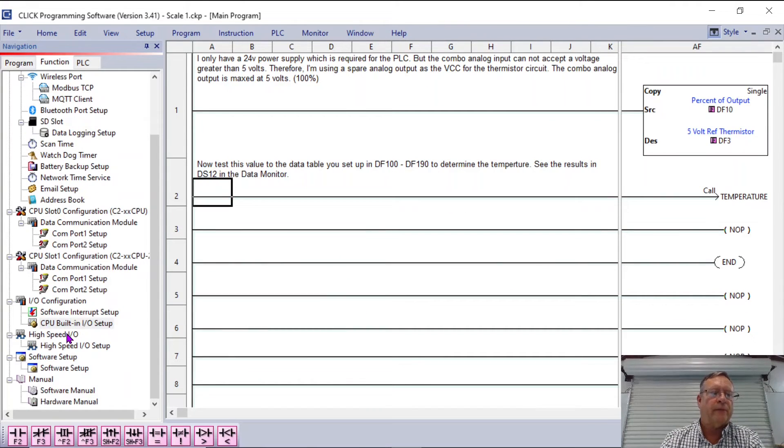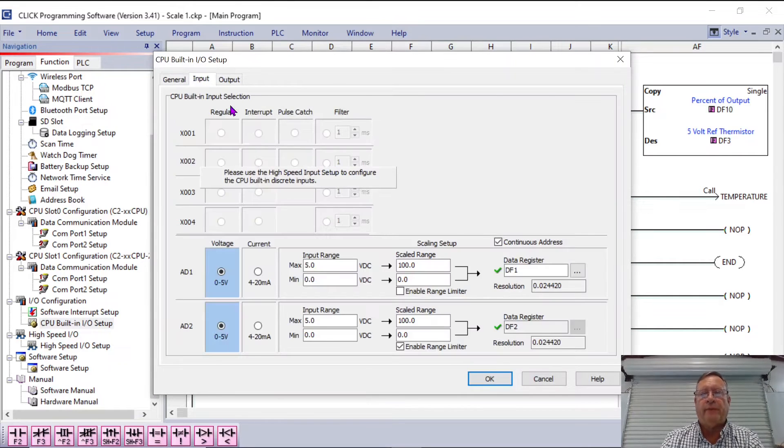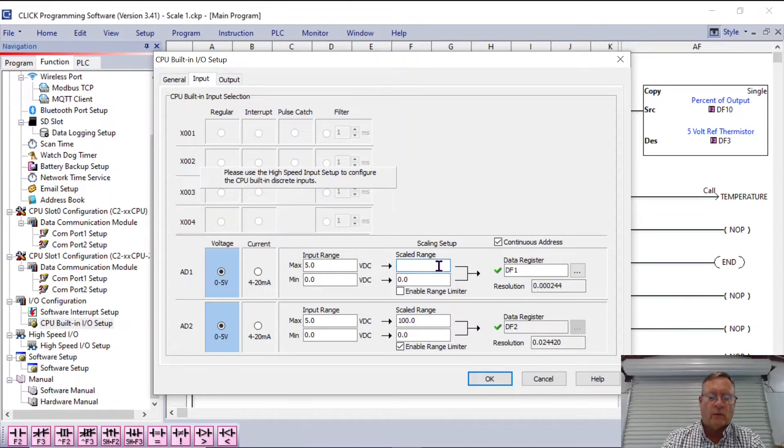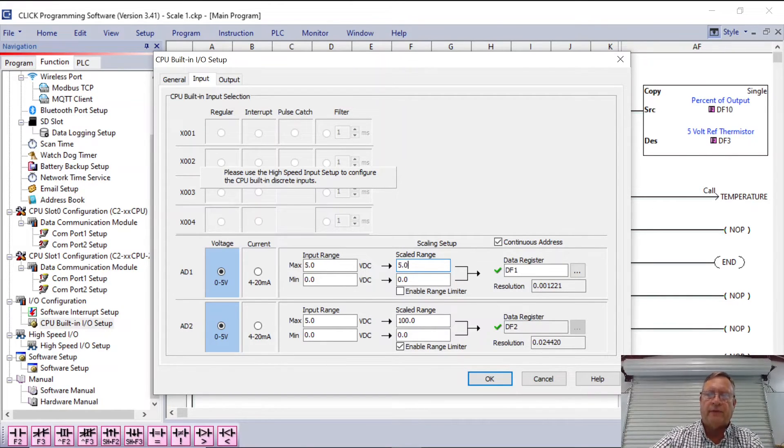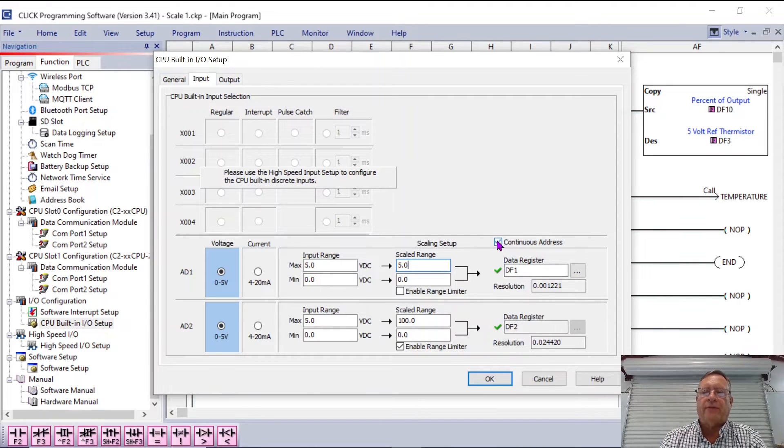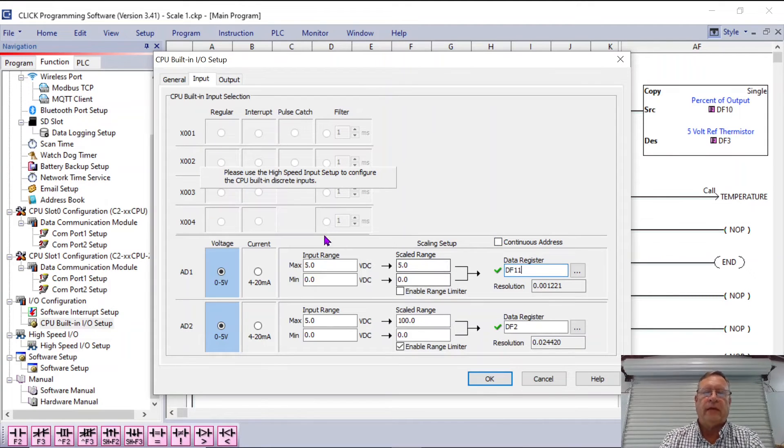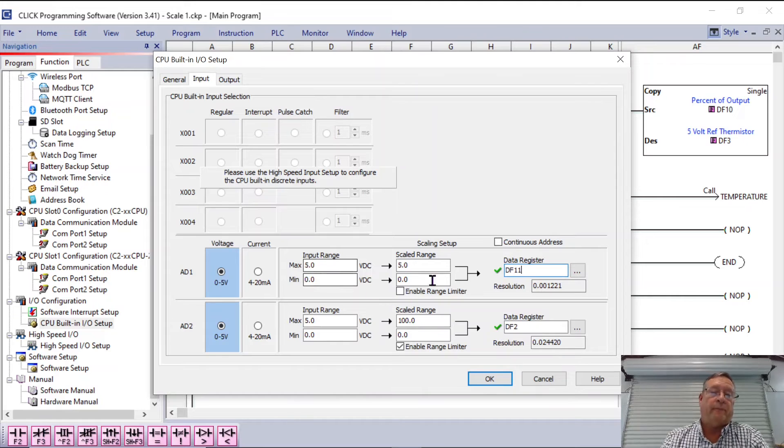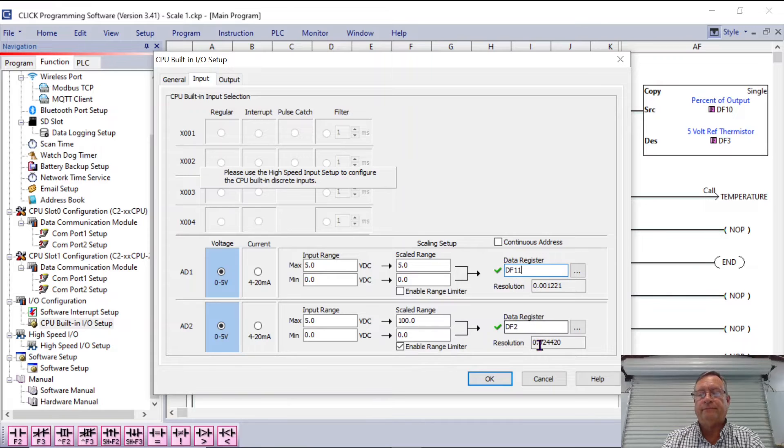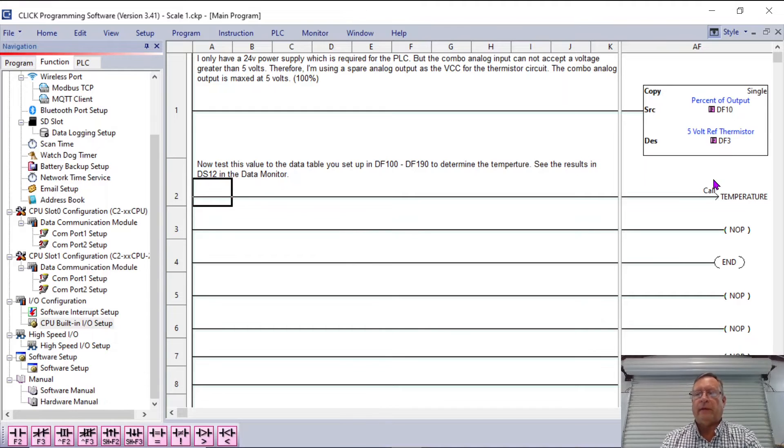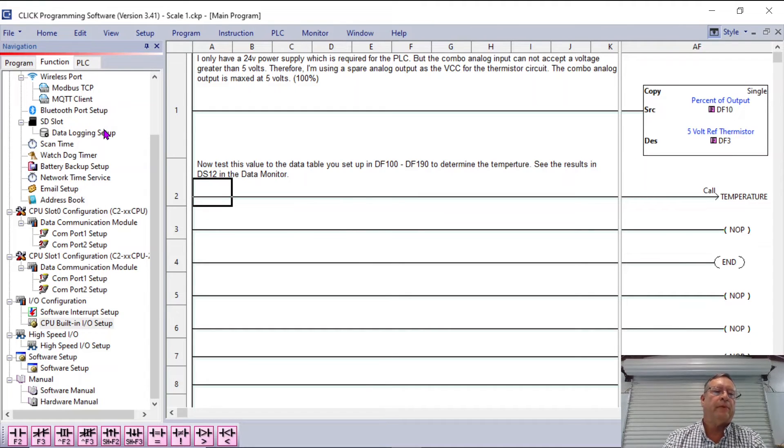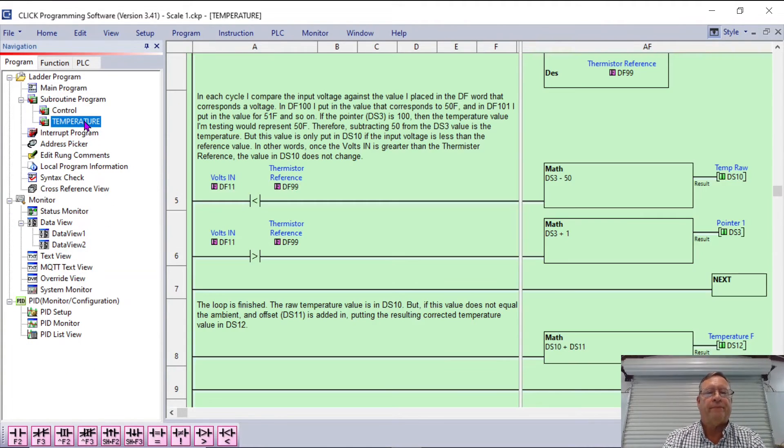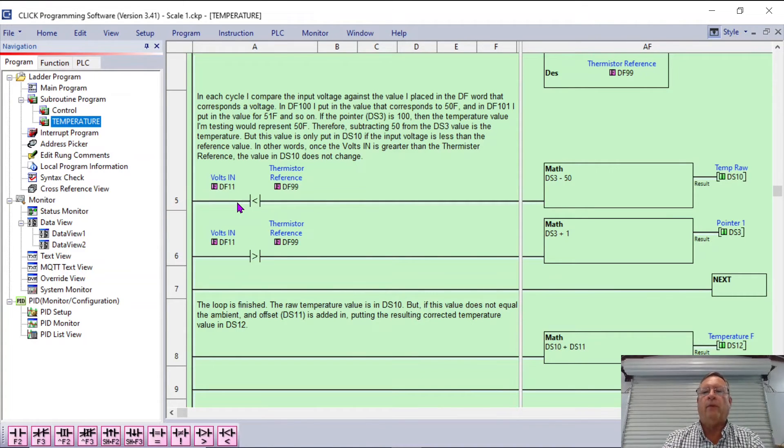Now I need to go back to my CPU analog input. I'll change this on the input to 0 to 5 volts now, since I'm not using this scaling that I was doing on rung number two, 5.0. Now let me turn this continuous address off. I'll change this to DF11. So now I'm taking whatever my analog input is, 0 to 5 volts. I'm bringing that into a scale of 0 to 5 volts, and I'm putting it into DF11. Okay. I've deleted the rung that we had here for my scaling that was inside the program. Go back to the program. And now my compares are still going to be with DF11, just like I've done before.